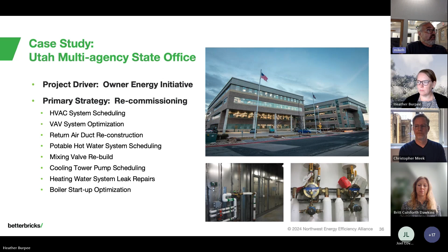The primary strategy here was a whole series of operations and maintenance moves, or what I'm calling recommissioning moves, touching on a lot of the existing building systems, from the HVAC systems to the potable hot water systems to the central plant systems. I'd characterize this building as one that had all the opportunities available to it for potential high performance, but had a number of operational deficiencies that needed to be addressed.